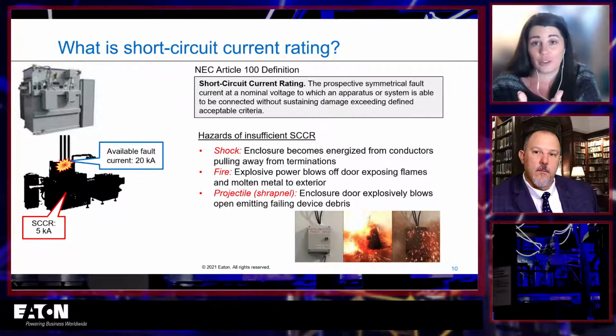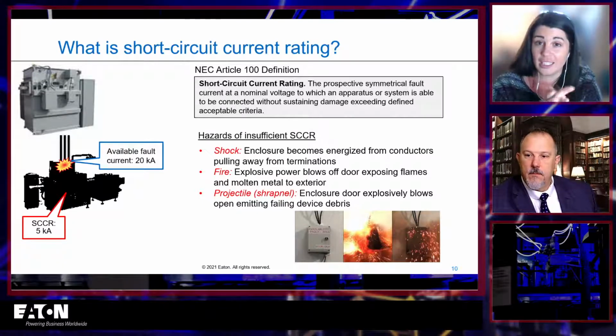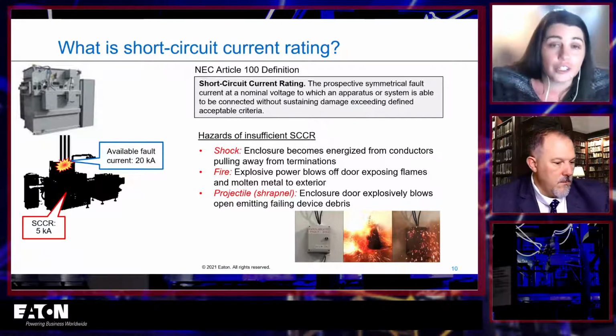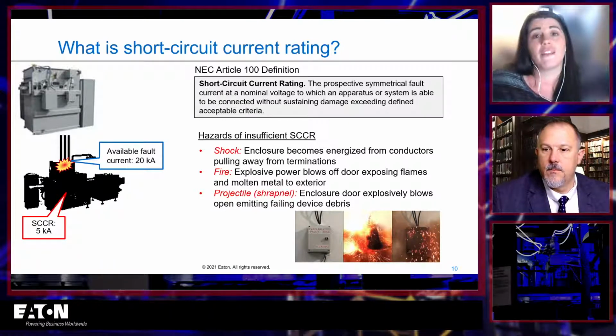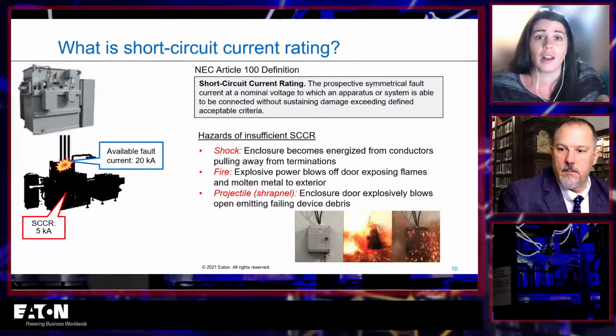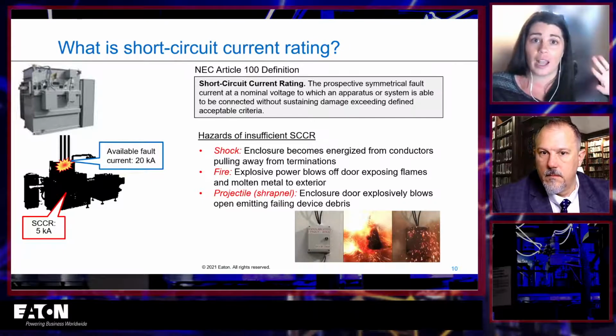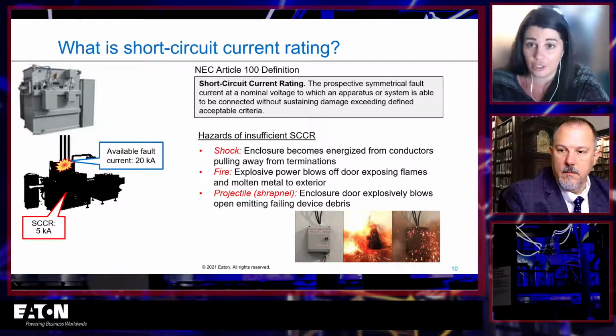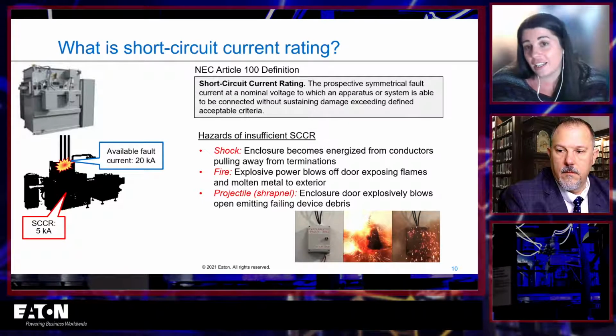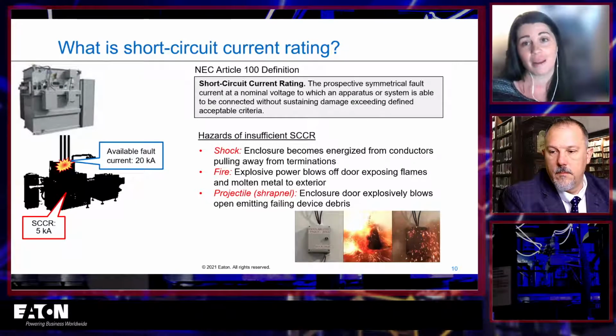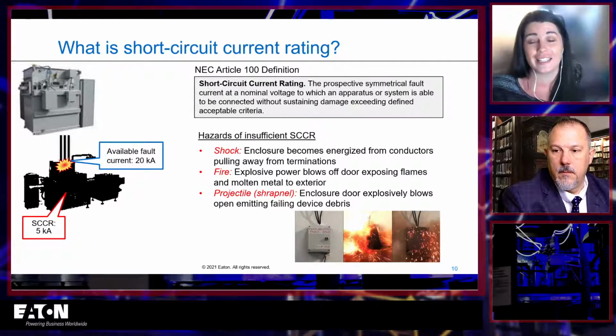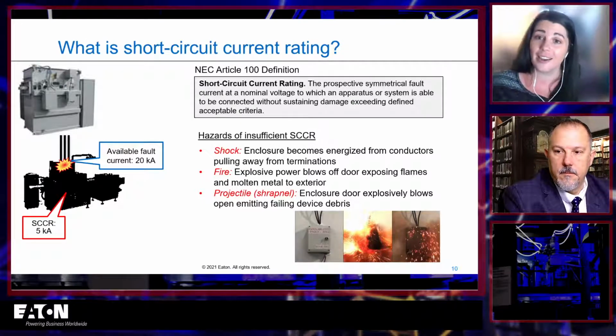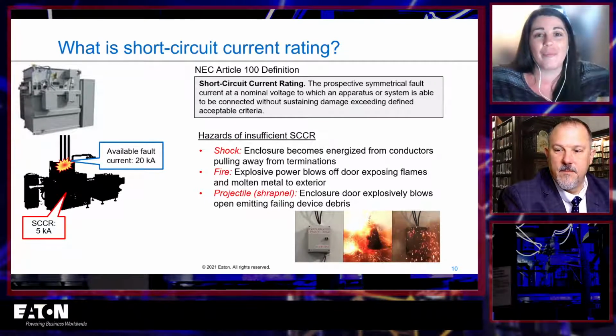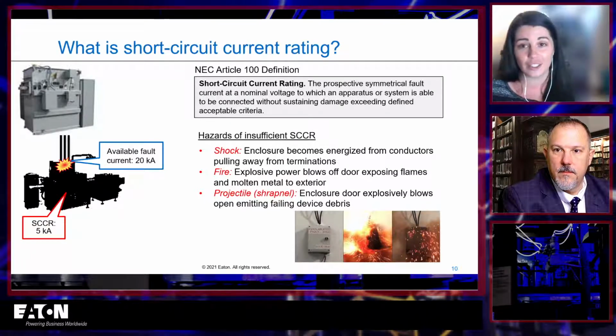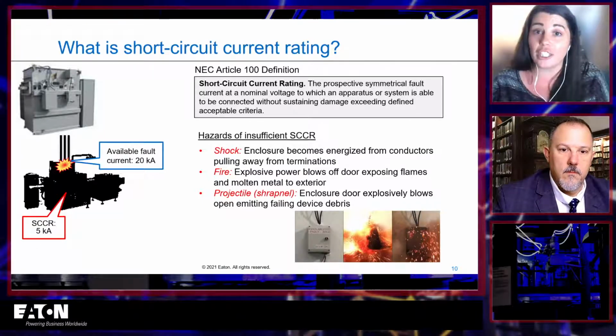And now we will talk about short circuit current rating and hopefully distinguish really how they are different. Short circuit current rating, by definition, is the prospective fault current that a piece of equipment, an apparatus, can be connected to. So how much it can see without sustaining damage exceeding acceptable criteria. That's just my favorite part of the definition, right? What is an acceptable amount of damage? What isn't? And who gets to decide? So it's how much it can be connected to without sustaining too much damage.